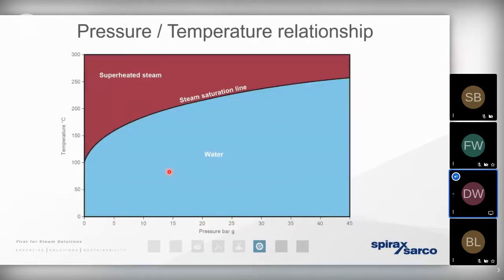Steam tables also tell us that there's a pressure to temperature relationship. We know at zero bar gauge, water boils at 100 degrees. And therefore, we can say that the temperature of the steam that's produced at zero bar gauge is also 100. If we're producing or distributing steam at a higher pressure, let's say 10 bar, the boiling point is higher, and therefore the temperature of the steam is higher. So this demonstrates the benefit of being able to manipulate the temperature by controlling the pressure.